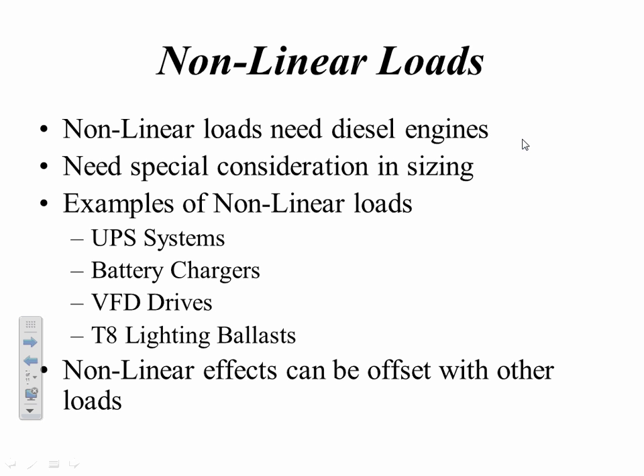transitional things happening with natural gas, and there were a lot of issues with running nonlinear loads at first. They've kind of gone away as the industry has progressed. I call that kind of a system problem. In other words, nonlinear load was running fine and the diesel engine generator is running fine, or the natural gas engine generator was running fine. But when we switched the two online together, there were issues between the two. So those have kind of gone away since the advent and the perfection of nonlinear systems.